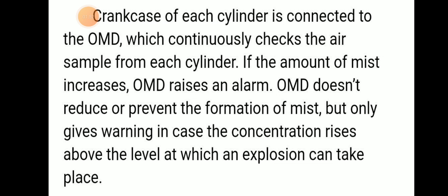Here the crankcase of each cylinder is connected with the oil mist detector. They will continuously check the air sample of each cylinder. If the amount of oil mist increases, the oil mist detector alarm will be raised. The OMD doesn't stop or prevent the formation of mist, but gives a warning in case the concentration rises above the level at which an explosion can take place.